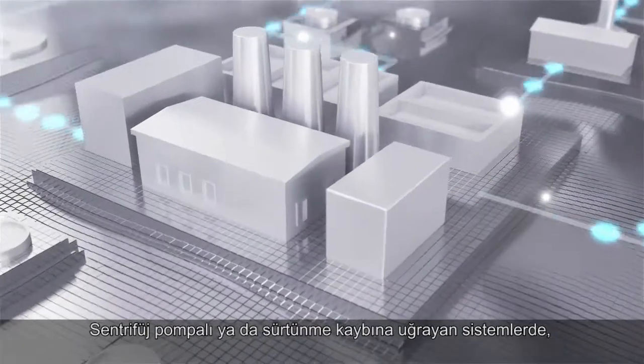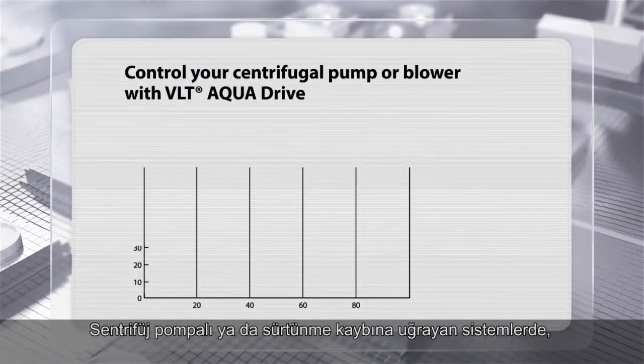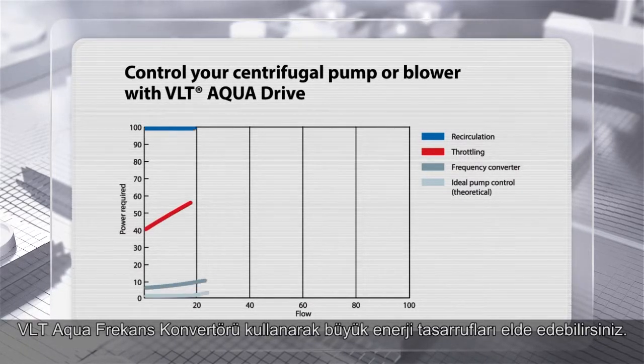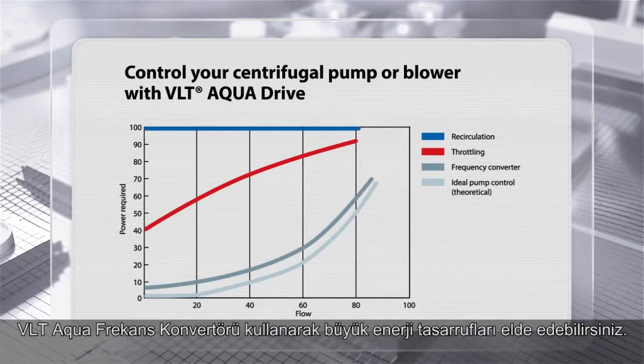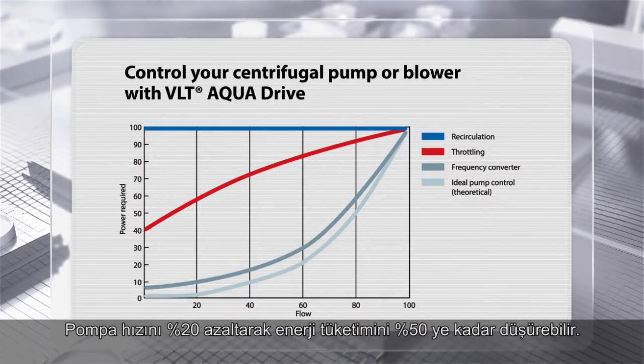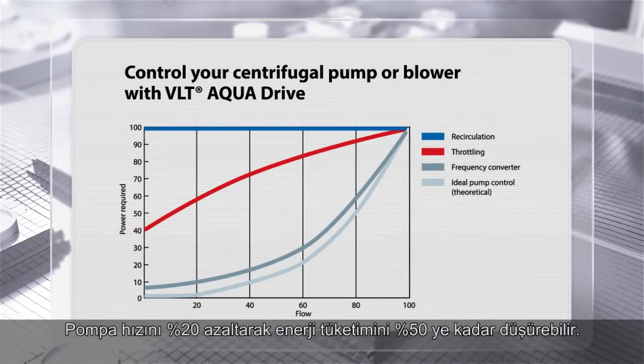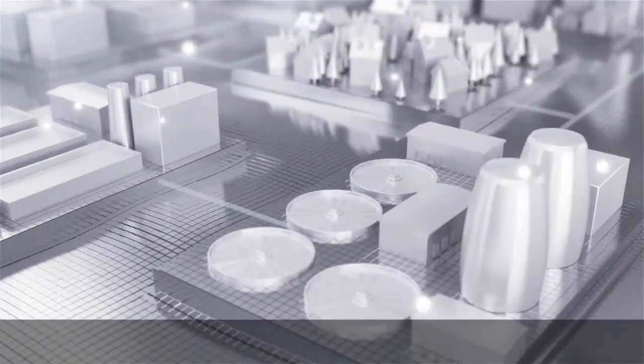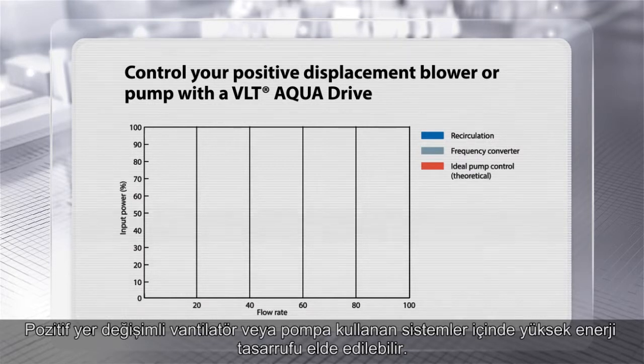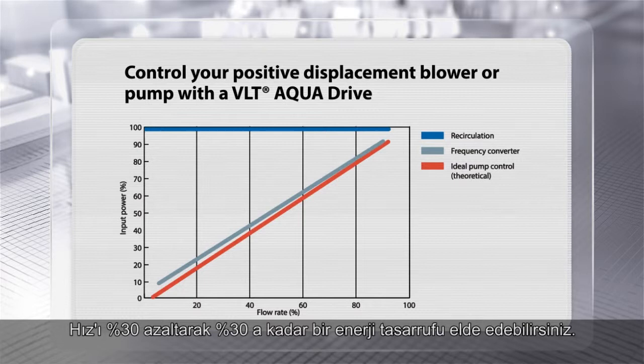In a system using centrifugal pumps or blowers predominated with friction loss, major energy savings can be obtained by using the new generation VLT AQUA Drive. Just a 20% reduction in pump speed can reduce energy by up to 50%. High energy savings can also be achieved in systems using positive displacement blowers or pumps — a 30% reduction in speed can deliver up to 30% energy savings.